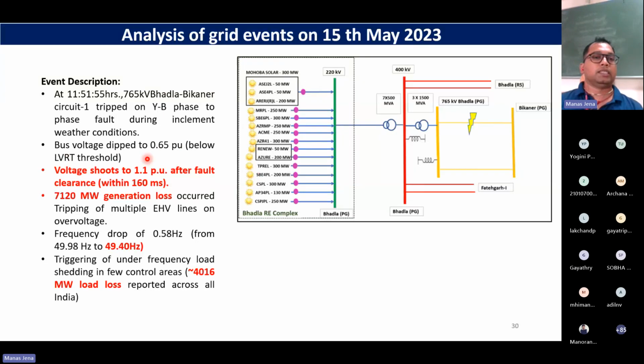The bus voltage dipped to 0.65, which is below the LVRT threshold, because of this fault. Okay, and I'll show you a few diagrams. You will see that, surprisingly, after the fault clearance, the voltage shoots to 1.1 per unit. And this is a very natural event. It's not a very strange event, right? A fault happens, it will happen. Protections are there to trip, isn't it? But because of this, so many other events happened, which was surprising.